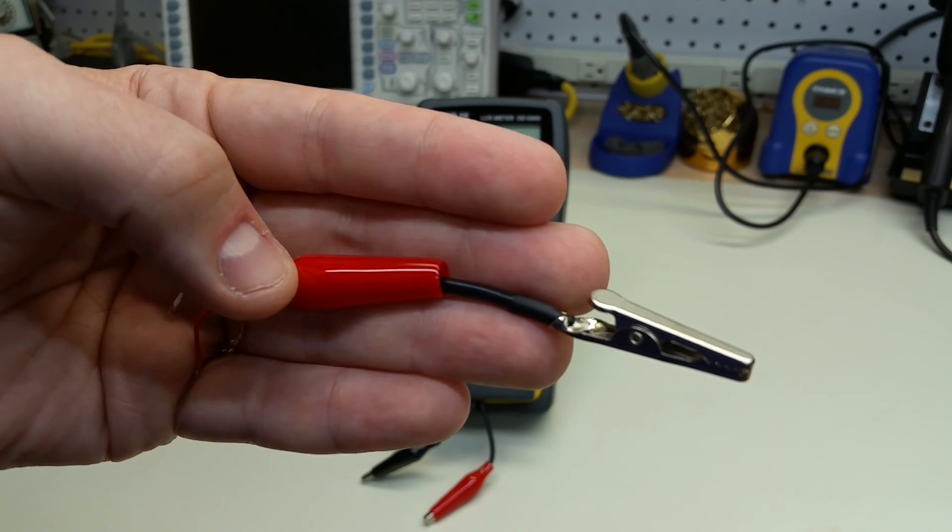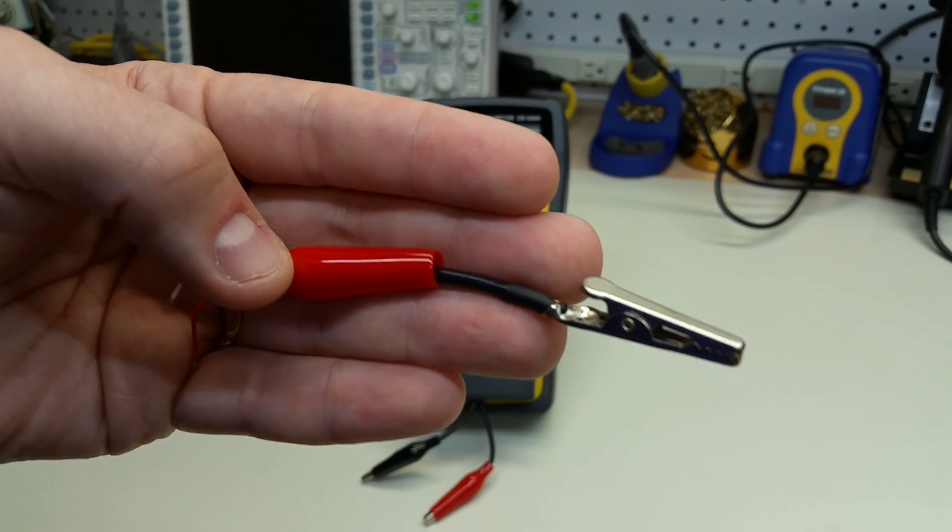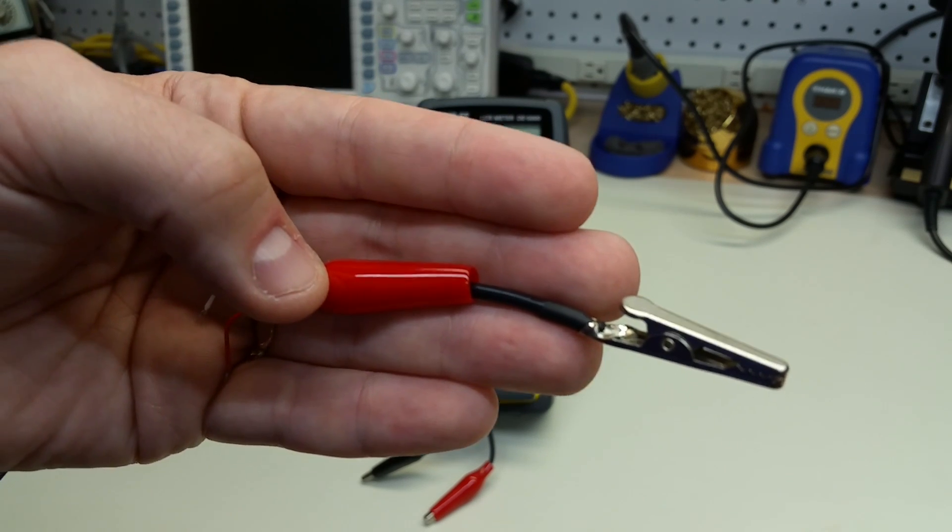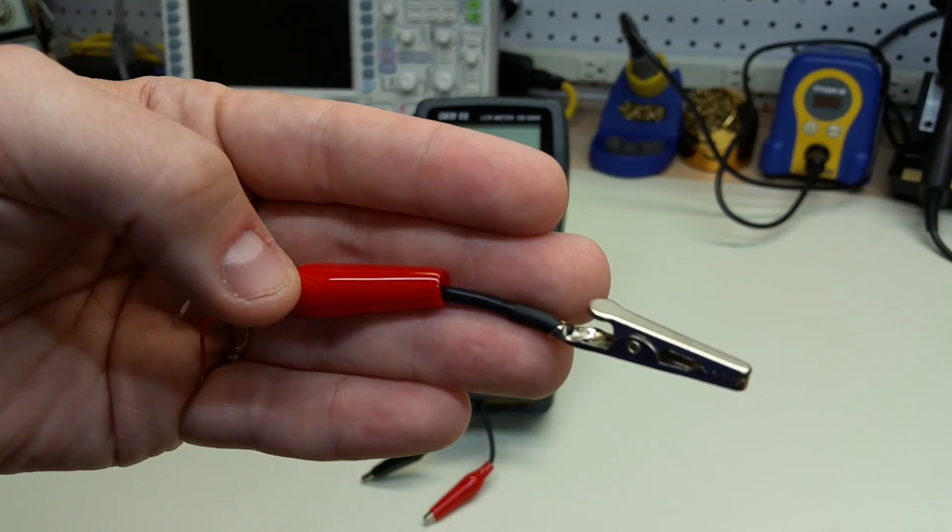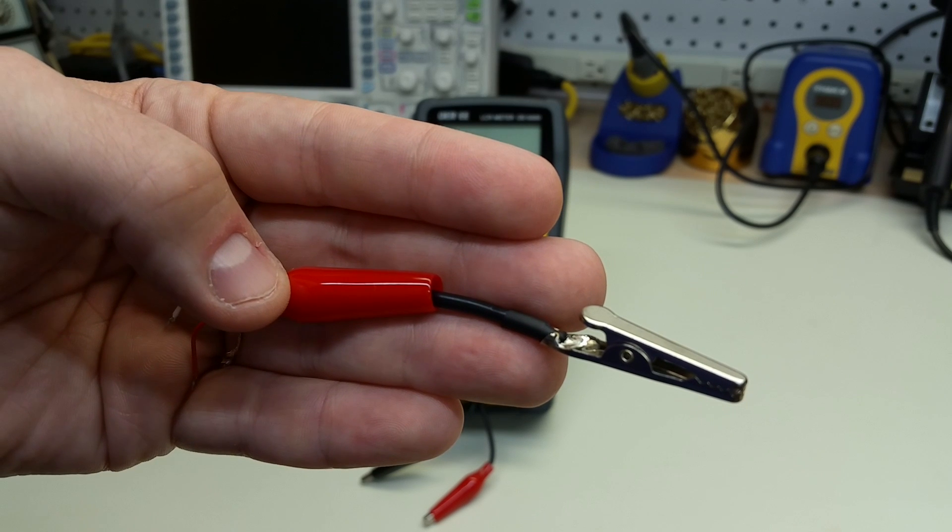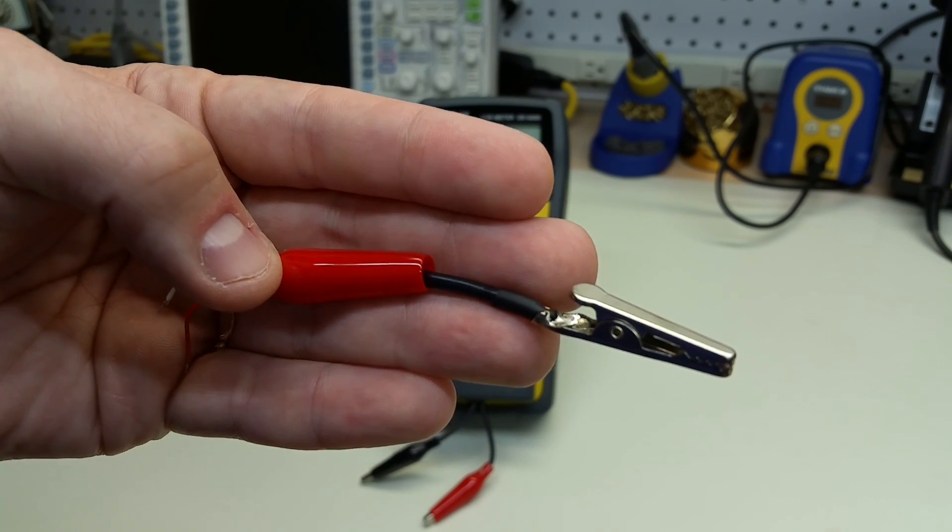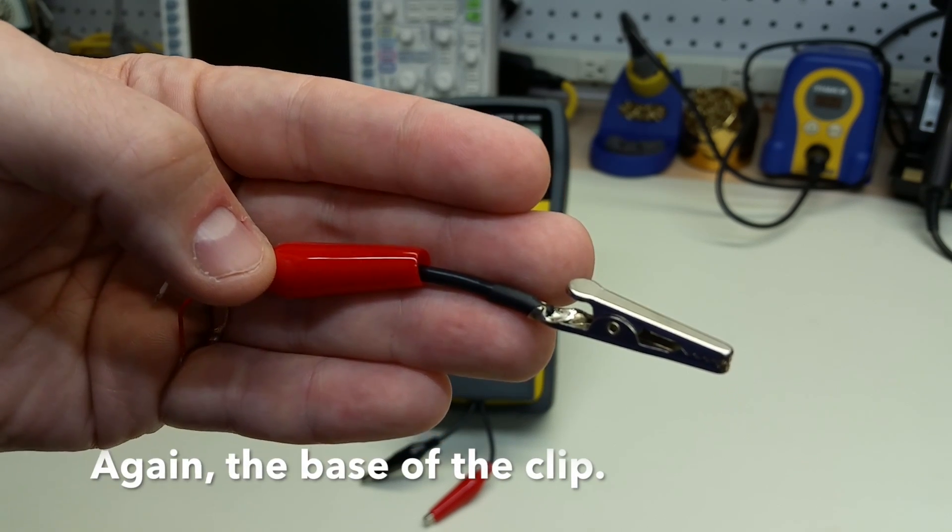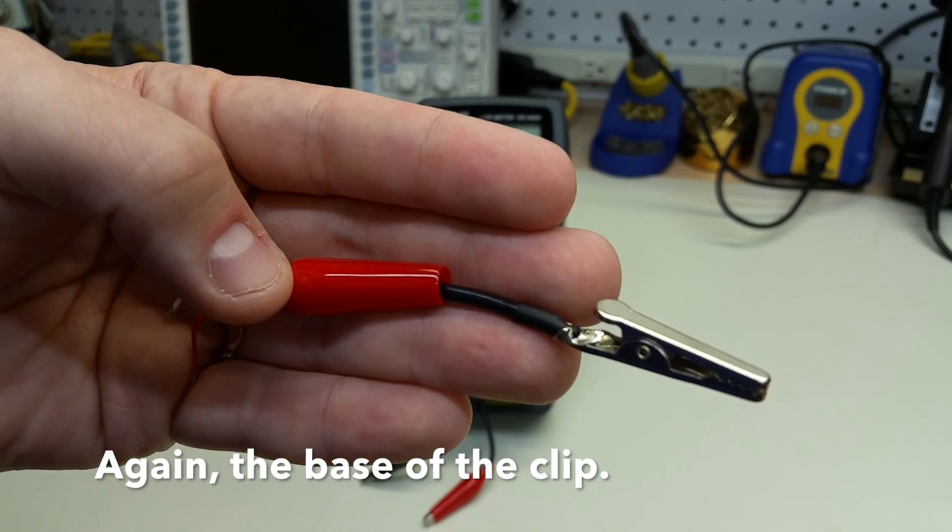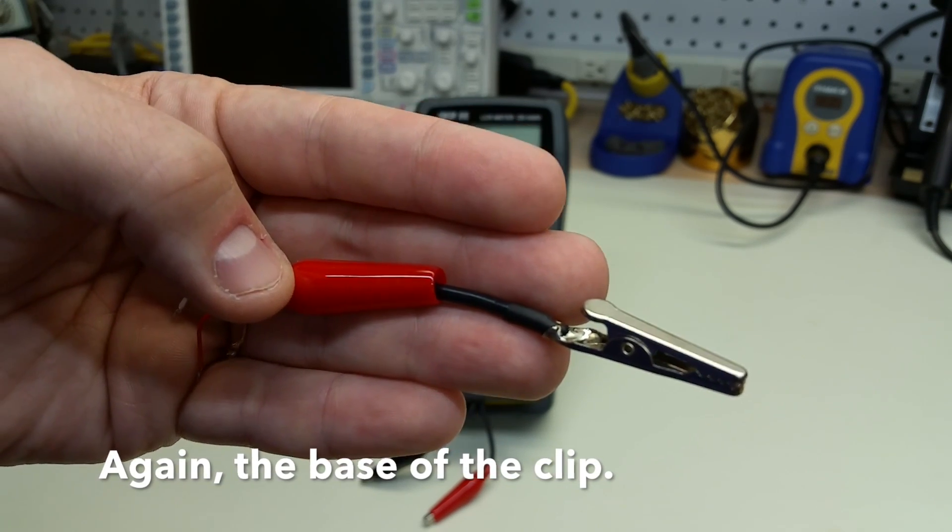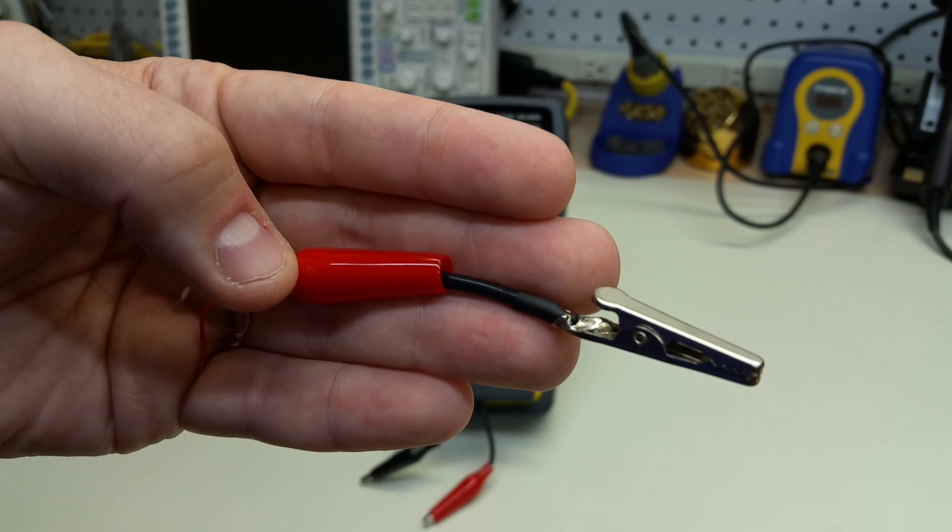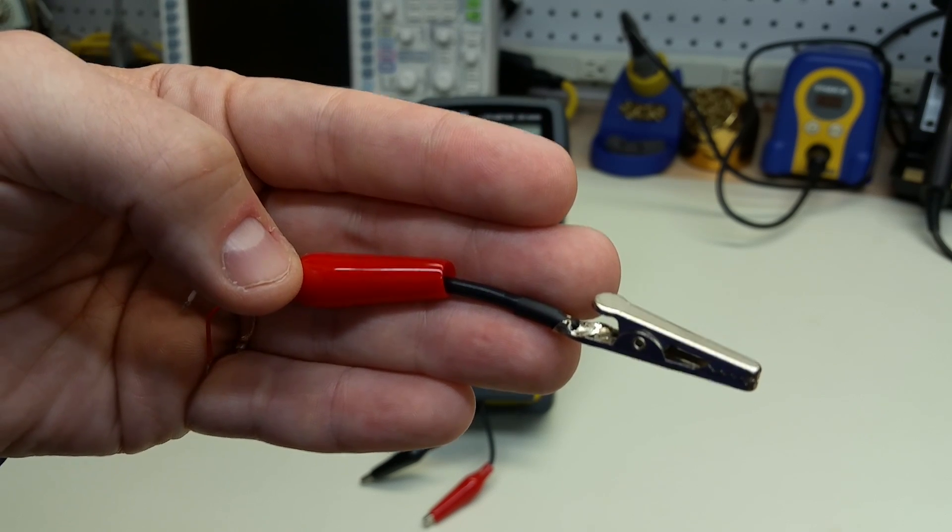This isn't a Kelvin clip because the current carrying lead is connected to the voltage sensing lead at the head of the alligator clip, and it's not kept separate until the point of the measurement.